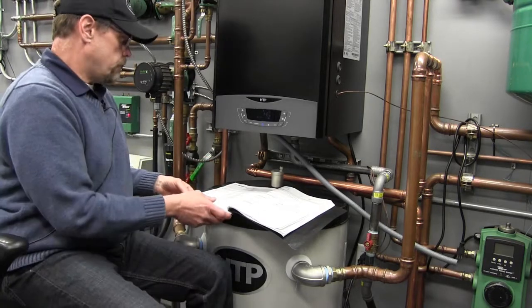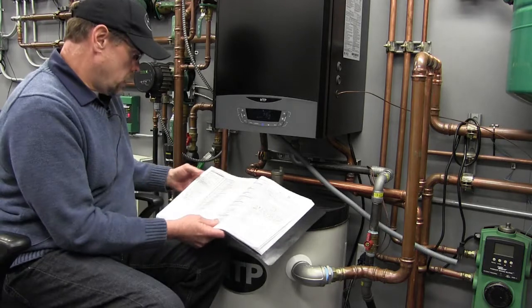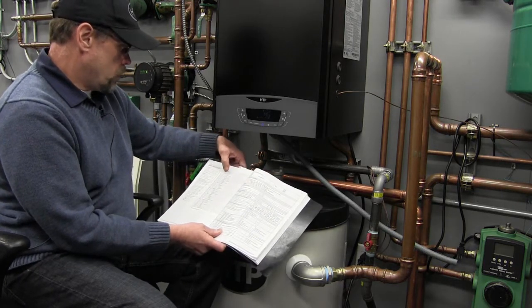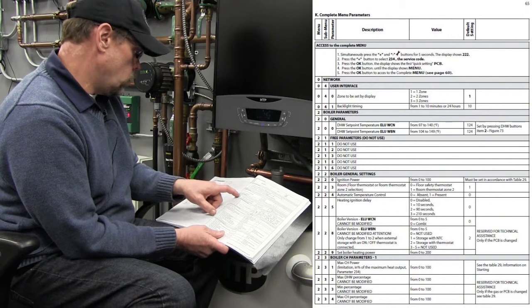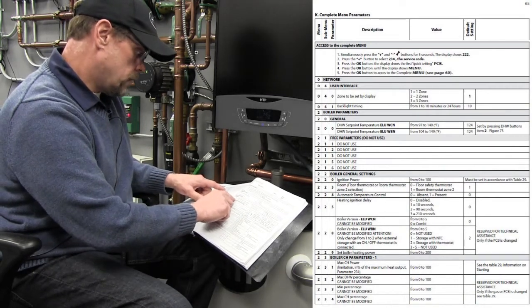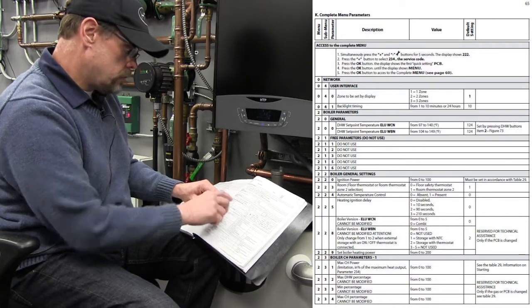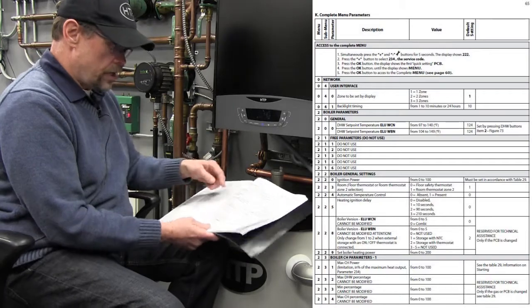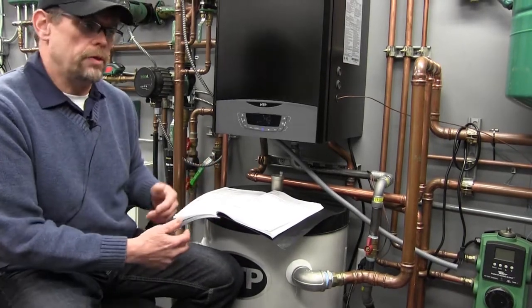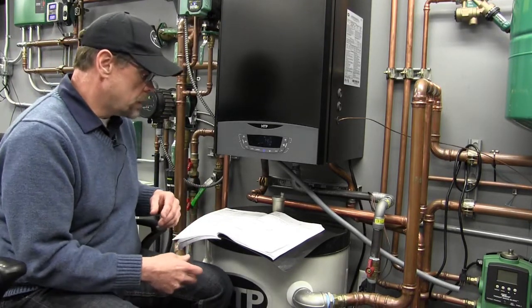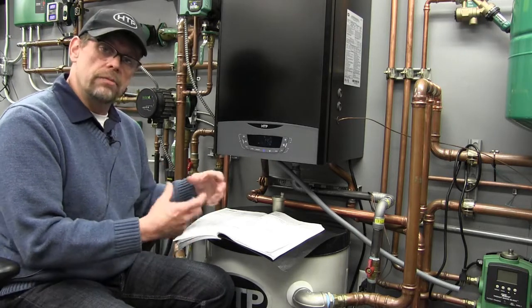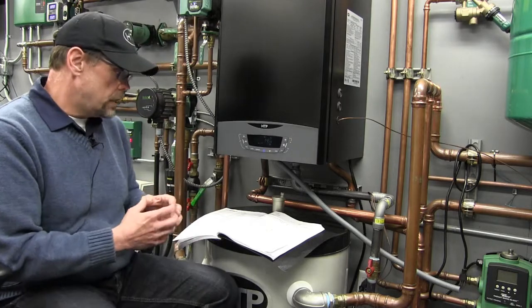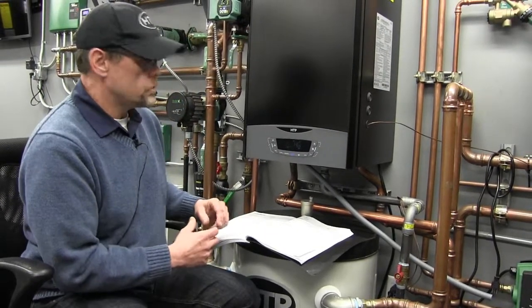So to clarify, if I go into the first set of parameters, the boiler parameters are listed in the 200 series. I go over to my page 65 and I see here 2.0 general, and we go down 200, 210, 211, 212, and each function, of course, in some cases, some of them say we're not using this function. It could be for future use. And in some cases, they'll be addressing either an application we're using or maybe it's denoting a function that we might not be using, depending, of course, on application. So what we'll have to do is kind of break out these segments individually and talk about the key functions and how they interrelate to allow your boiler to run safely and efficiently.